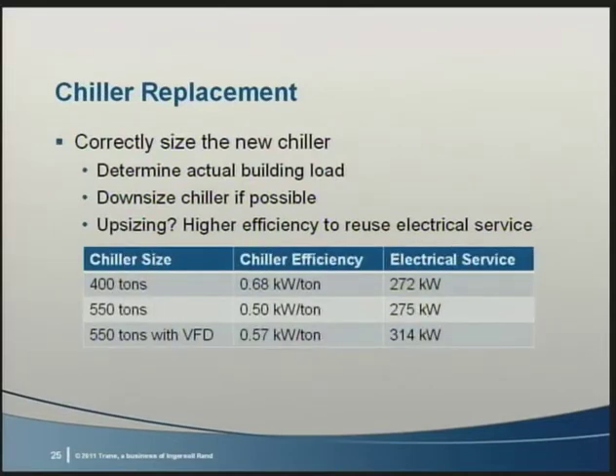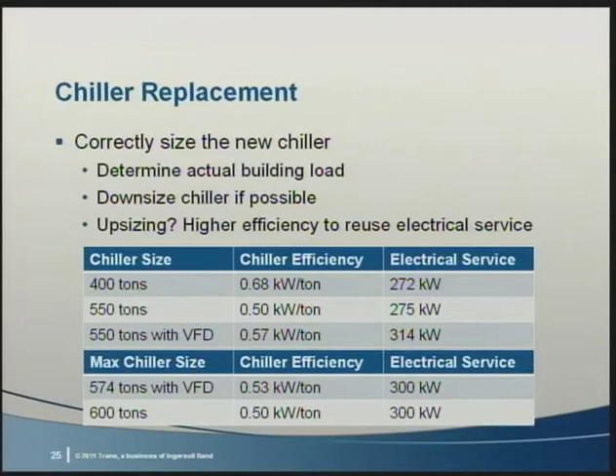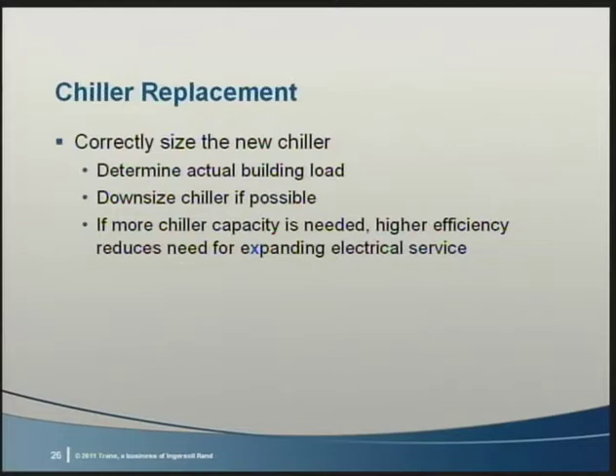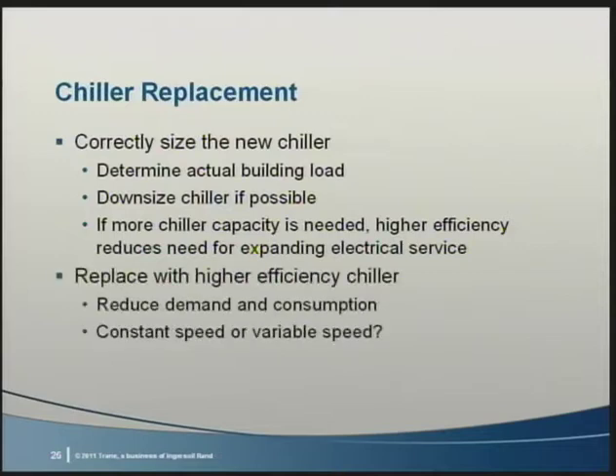Let's say you have a 400-ton chiller that's 25 years old and the nameplate says 272 kW. That's about a 0.68 kW per ton. If the capacity required is now 550 tons, a new chiller at 0.5 kW per ton full load will need about the same electrical input. That could easily bring the job back into budget. But if you want to have a variable frequency drive, a similarly priced chiller would require a larger electrical service. Or for a given electrical service, you might back solve for the largest chiller available to maximize chiller capacity with the existing service. Besides electrical service size, to reduce energy use and cost, a higher efficiency chiller can reduce demand and consumption charges, whether it's constant or variable speed.